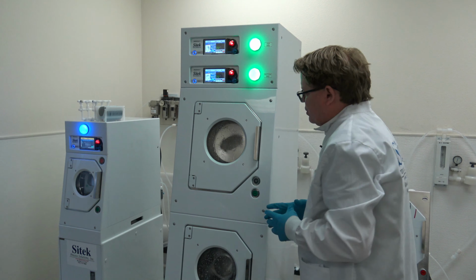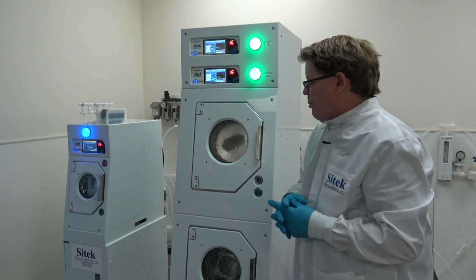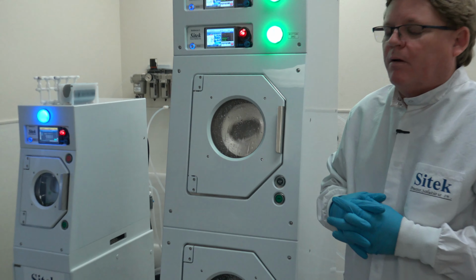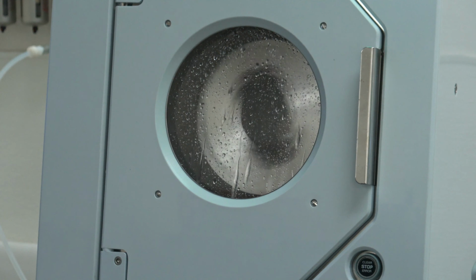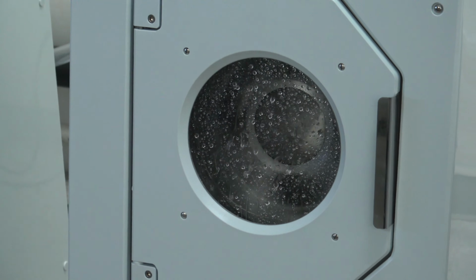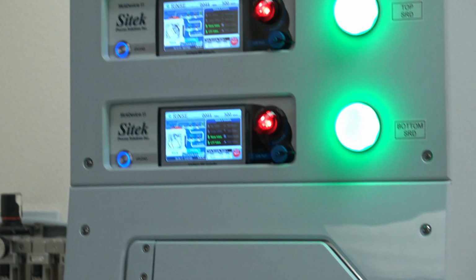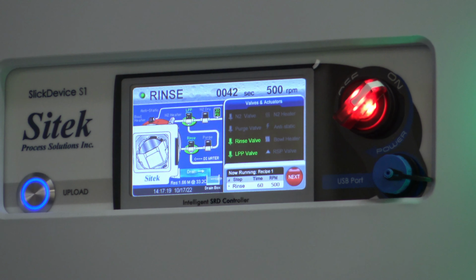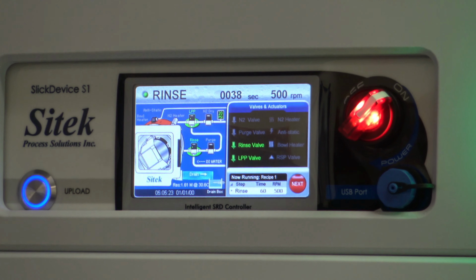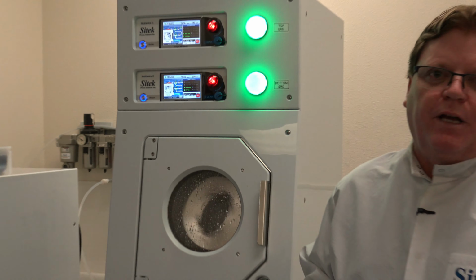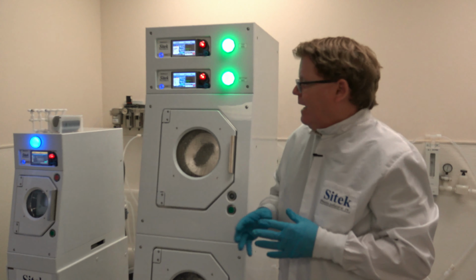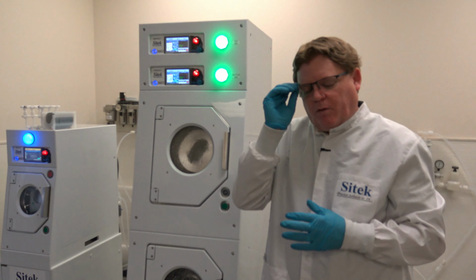It would have done a traditional SRD process, which would be a rinse, which you see now. It'll then go into a purge, which blows the DI water out of the lines. That allows no water to drip back during the dry cycles. We'll go into dry one, which is a high RPM dry, short duration, and then dry 2, which is the low RPM, meant to use the N2, the heater blanket, centrifugal force, and anti-static module for the final processing of it.